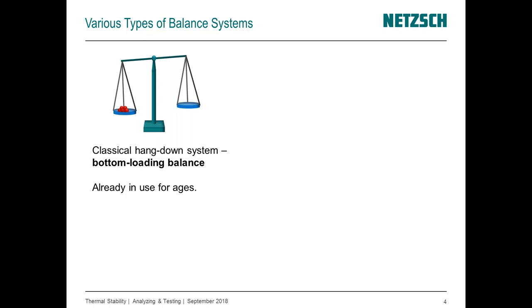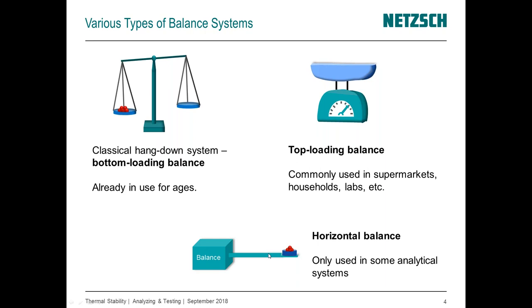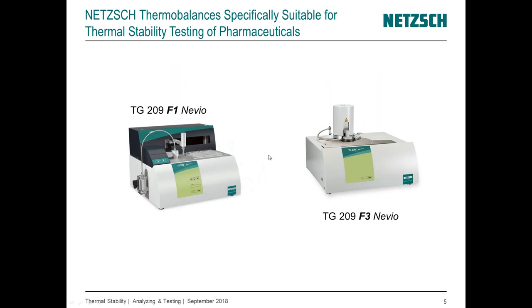There are different types of balance systems. The oldest, found several millennia before Christ, is the classical hang-down system where the balance beam is on top and the sample and reference hang from it. Another commonly used technique is the top-loading balance system, and there is also a system with a horizontal balance arm. I would like to focus today on the top-loading type because all the balances we produce are top-loading balances.